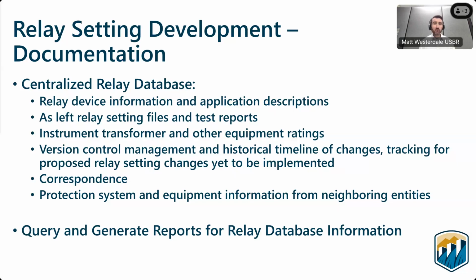It's also where we store our as-left setting files and test reports. We can link our relays with their connected instrument transformers or the equipment they protect, often providing information on ratings and nameplates. So it's a complete database and historical record of the protective system information for that facility.